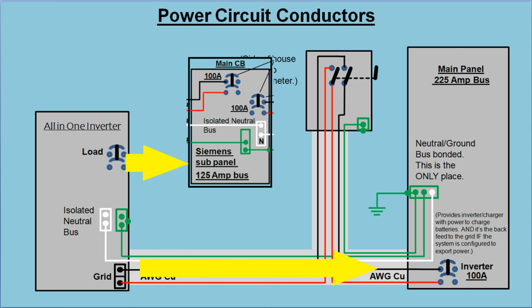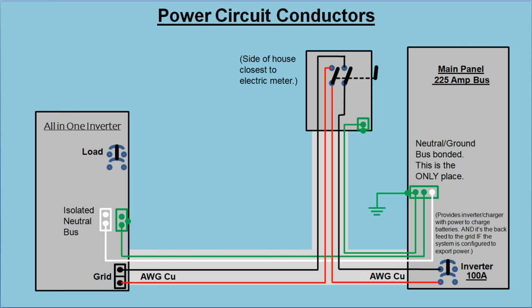However, this is also the grid tie circuit, so when the inverter has any unused power, it can export that extra energy through this circuit to the grid. So for example, if there's 25 amps coming in from the PV modules and the house is using 15 amps, the inverter can export the extra 10 amps out to the grid and make the meter run backwards. But we need to have a net metering contract in place with the utility company before we can legally do that.